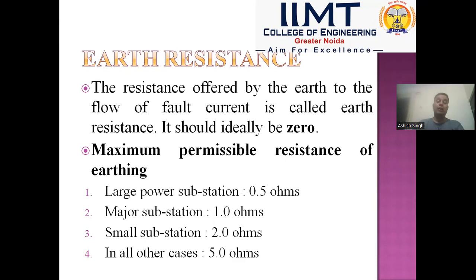given here. For a large power substation, the maximum permissible earth resistance should not be greater than 0.5 ohm, and for a major substation it should not be greater than 1.0 ohm. For a small substation it should not be greater than 2.0 ohm, and for all other cases, commercial buildings etc., it should not be greater than 5.0 ohm.